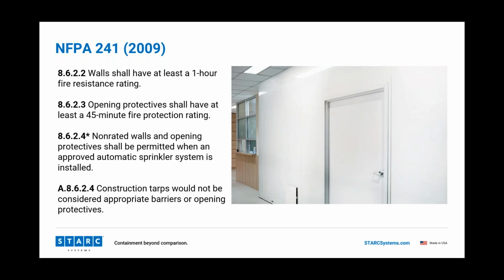So we use partial evacuation strategies. And this buys us the time, this 1 hour wall or the sprinkler system. One important note that we wanted to bring up here is that construction tarps are not appropriate barriers. I know that this is in the annex. I know it's a should not shall. However, it should be a shall. Boy, say that 10 times fast.